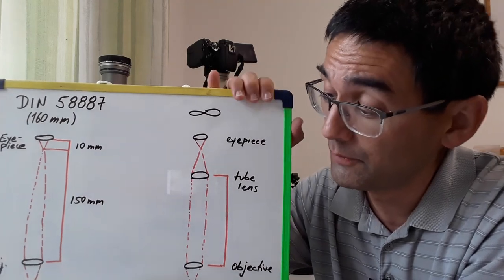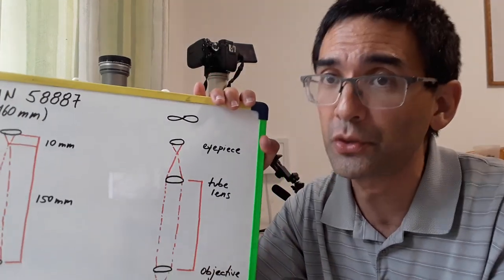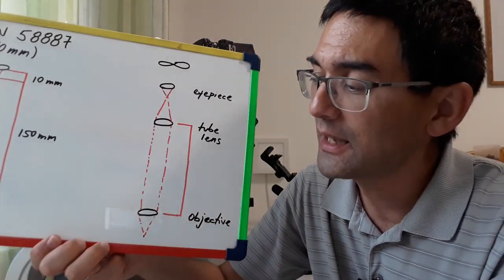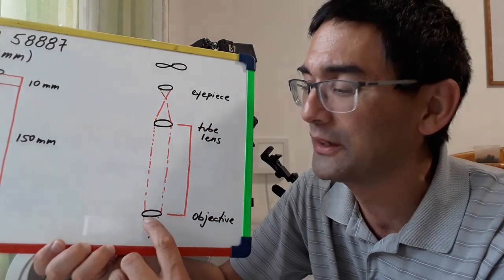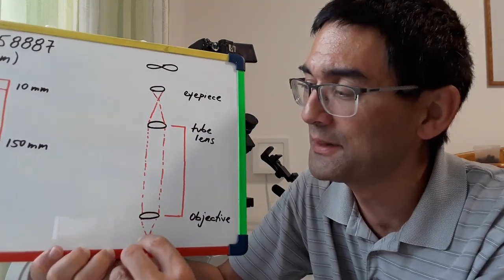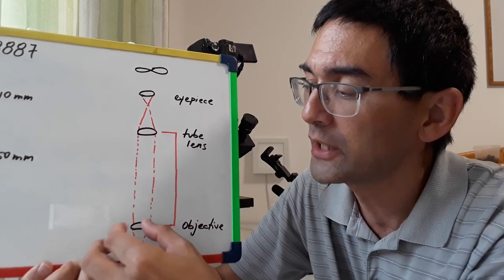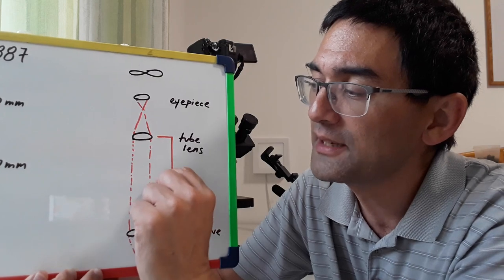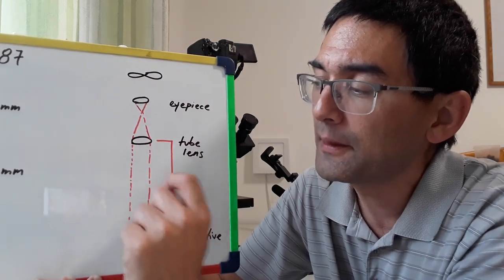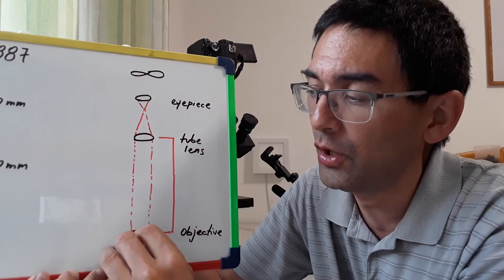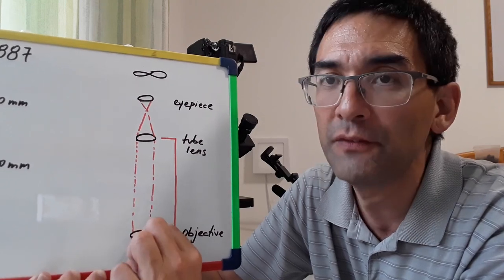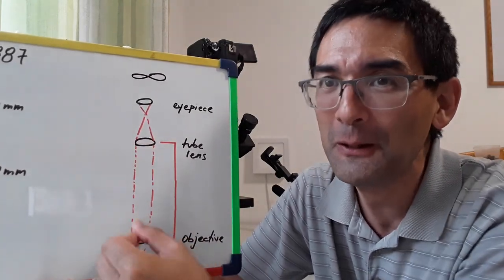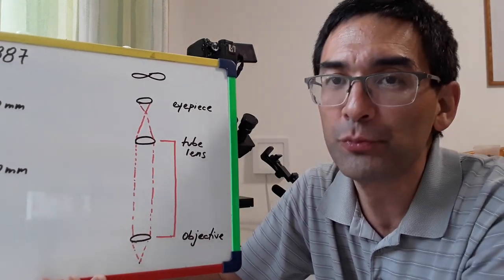And for this reason around, I don't know, 20 years ago or so, maybe 30 years ago, the first microscopes started to appear that have the so-called infinity objectives. In this case I've also only drawn one lens but in reality it's a system of lenses and what happens is that the objective now creates a so-called parallel light beam. So this means that if you place any filters in here then this is not going to change the focus.